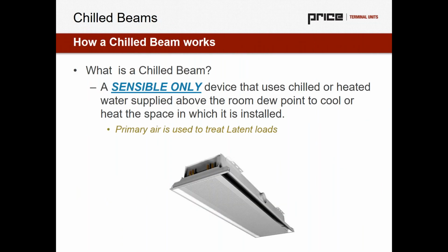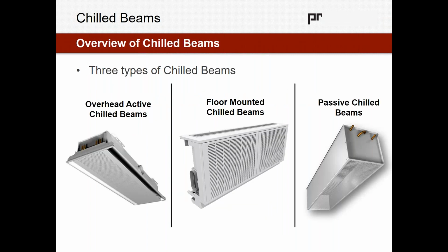So what is a chilled beam? Hopefully we're mostly familiar, but as a quick review, a chilled beam is a sensible only device, so it's not providing any latent cooling. The latent cooling is coming from the air handler and is supplied through an active chilled beam, for instance, but the intent of the chilled beam is that it's a sensible only device that uses chilled or heated water supplied above the room dew point to cool or heat the space in which it's installed. So that primary air is being used to treat the latent load, and the chilled beam is being used to treat that space sensible load.